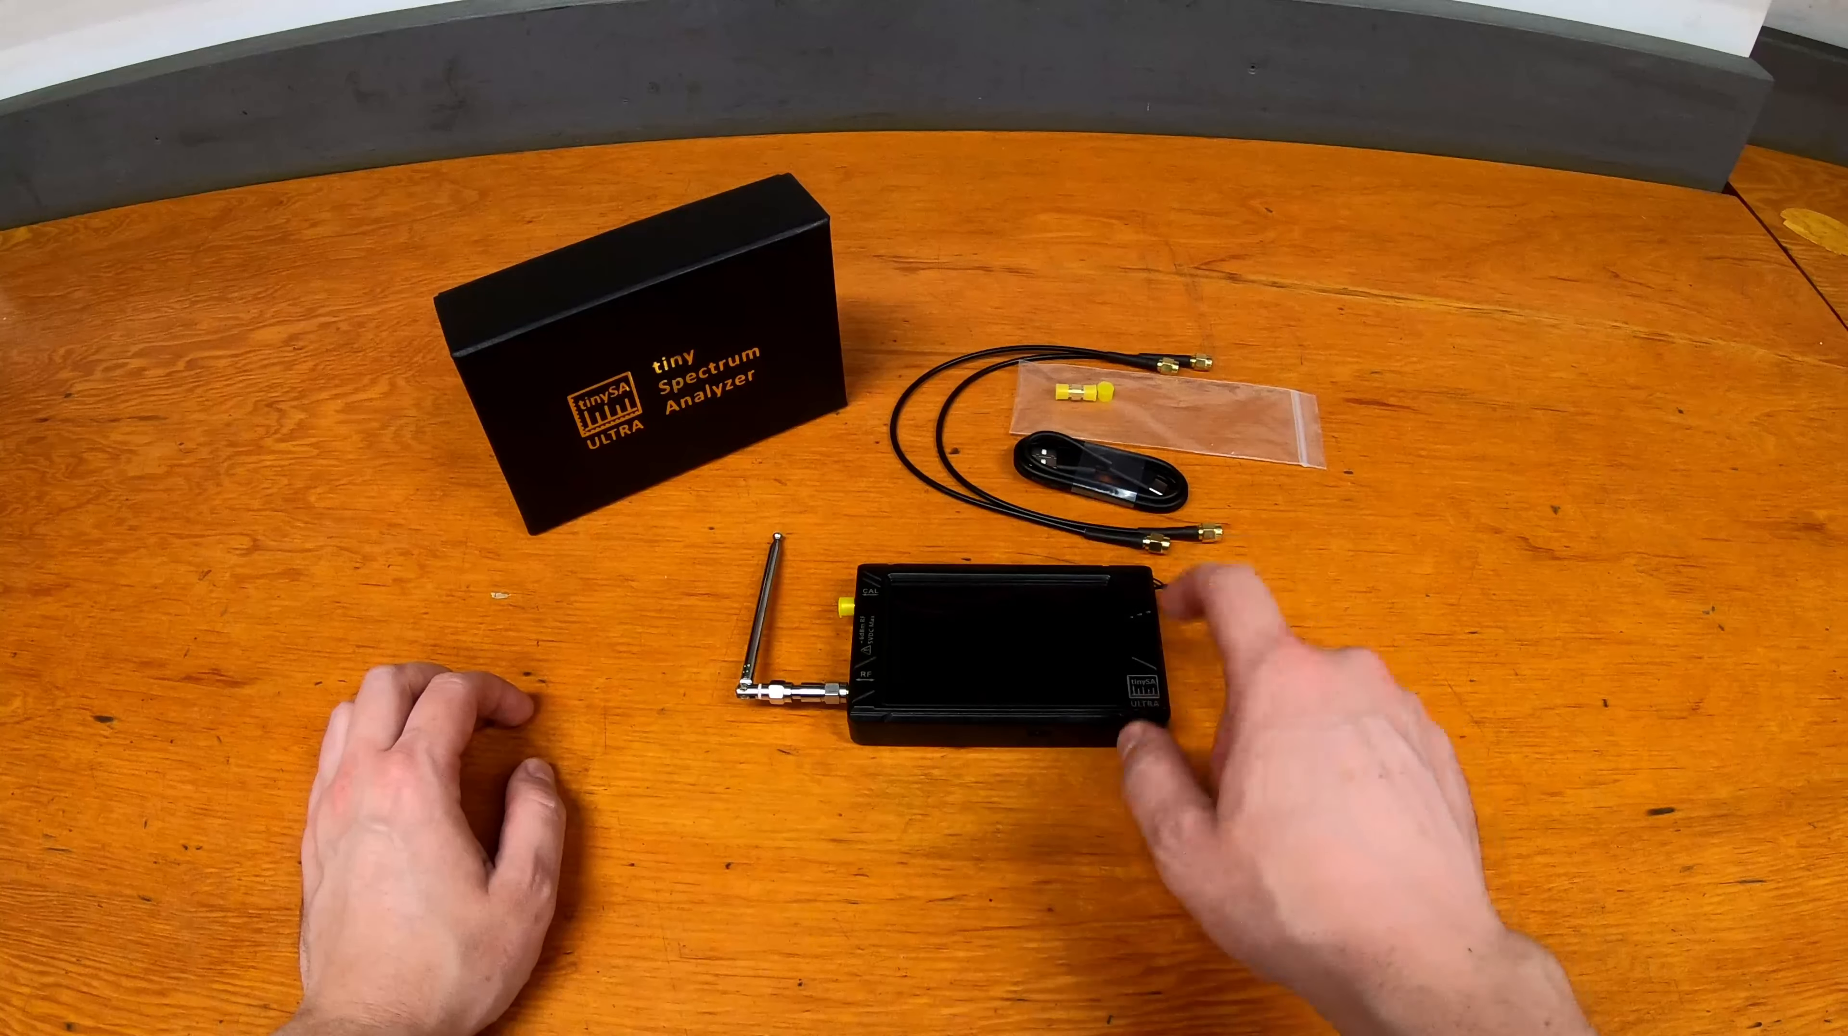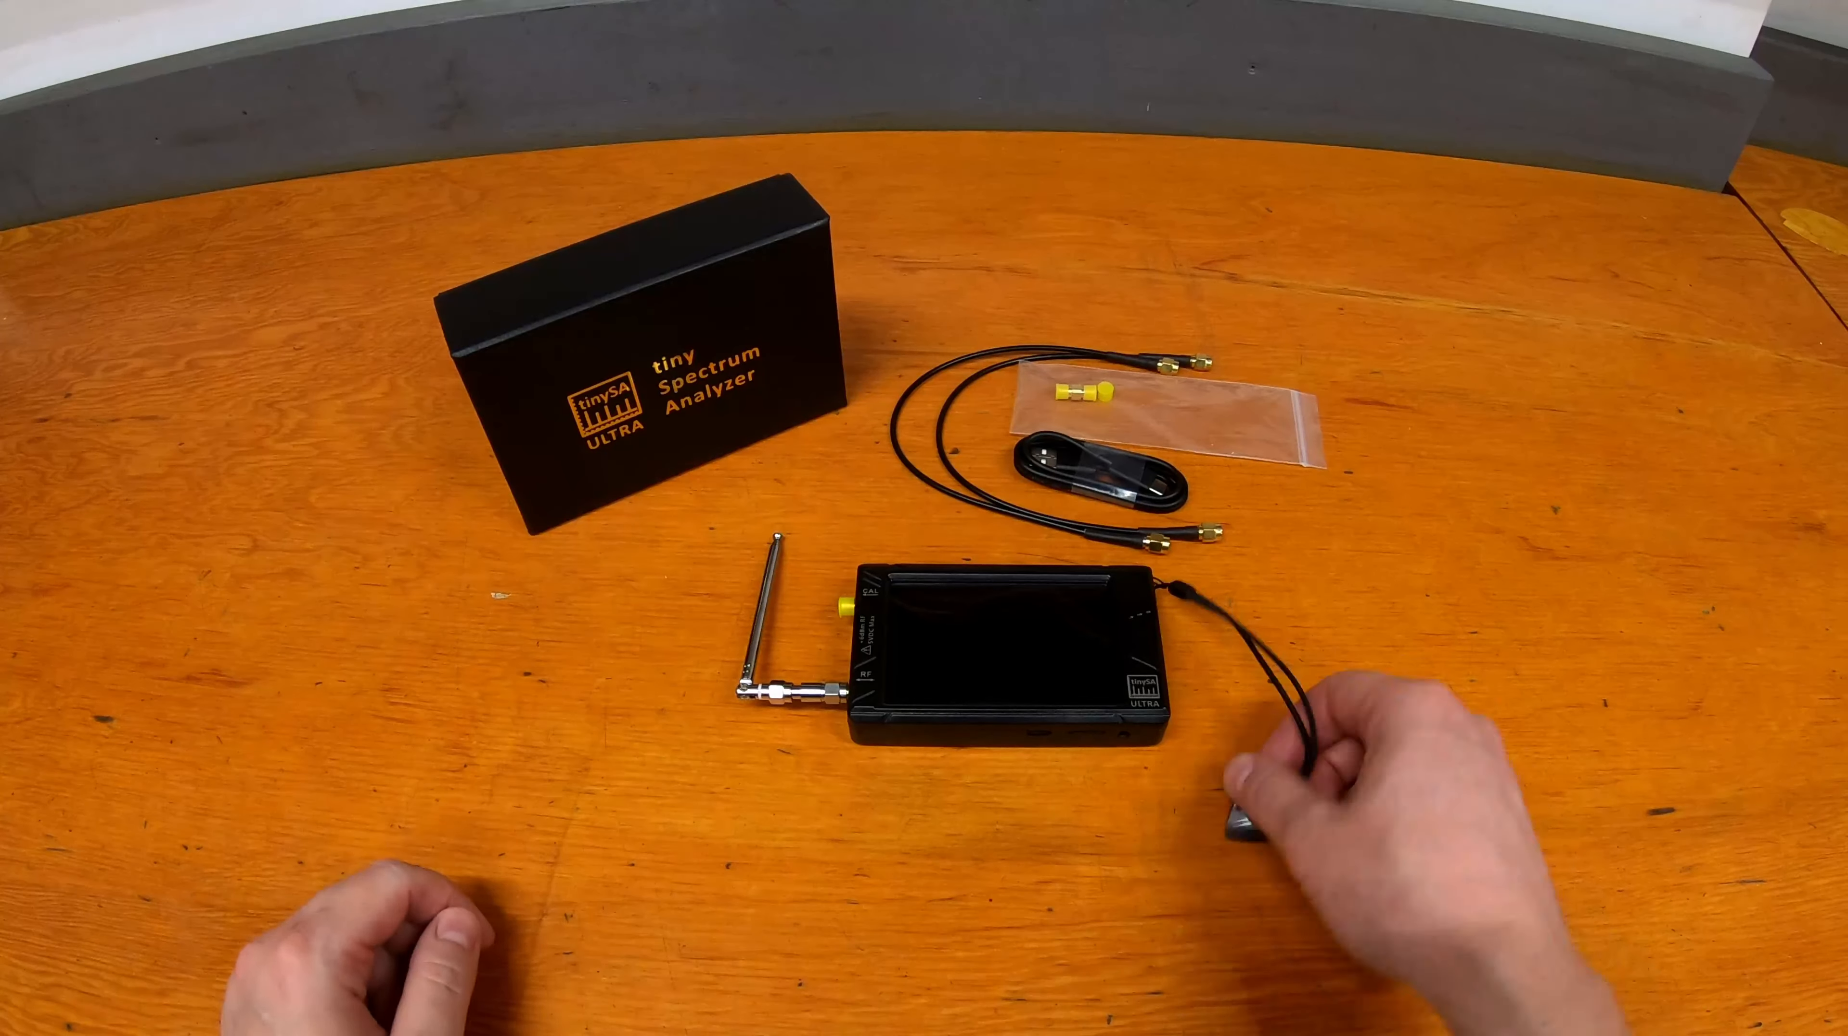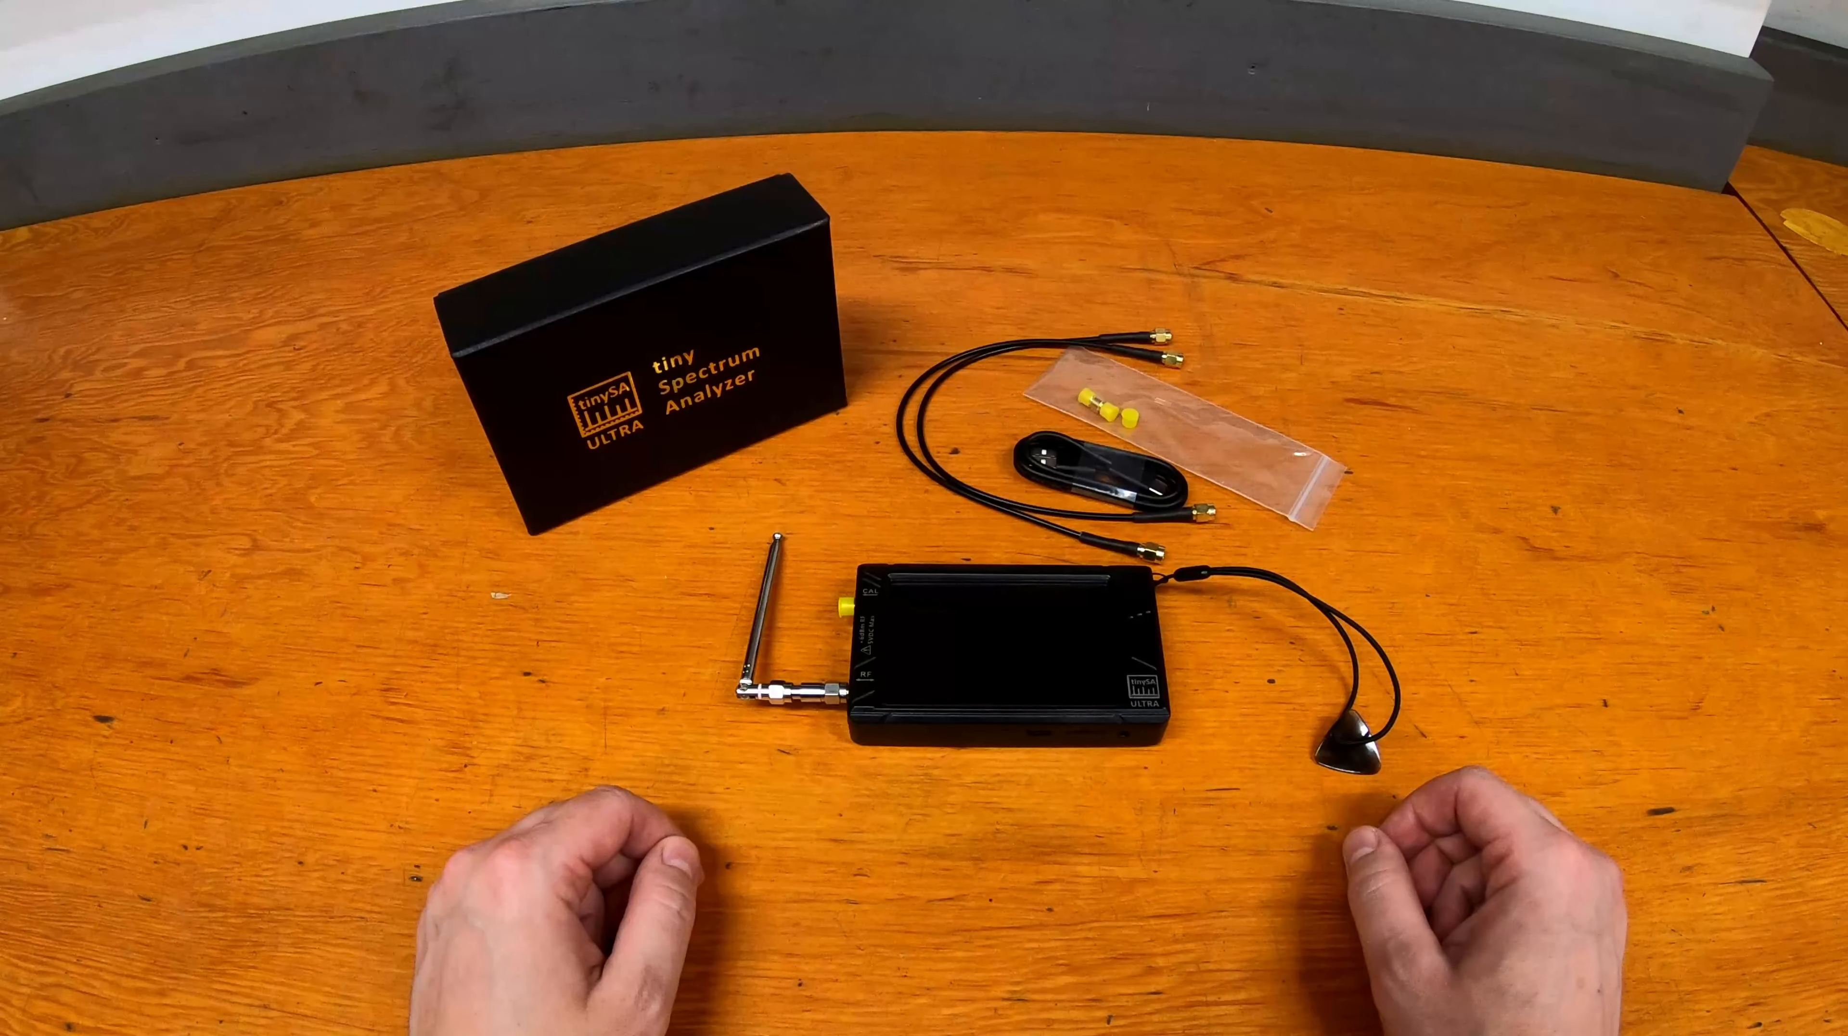And there's an adjustment in the software itself that says I've got a negative 20 dB external gain and it can automatically compensate it so you get a real reading despite the raised noise floor. Other than that, it does come with a lanyard with a little thing to help you poke the screen, a couple cables with a coupler as well. The cables can be used from the calibration to the actual RF port to be able to calibrate, self-calibrates the unit.